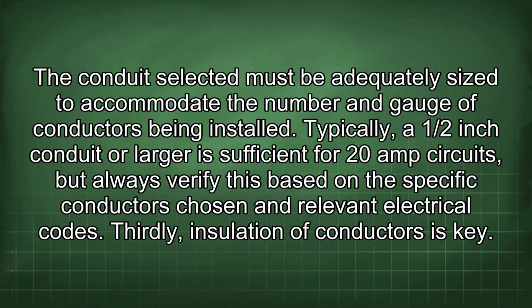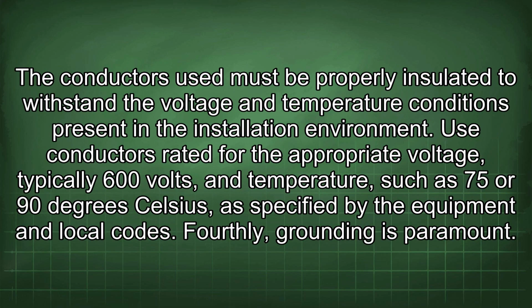Thirdly, insulation of conductors is key. The conductors used must be properly insulated to withstand the voltage and temperature conditions present in the installation environment. Use conductors rated for the appropriate voltage, typically 600 volts, and temperature, such as 75 or 90 degrees Celsius, as specified by the equipment and local codes.